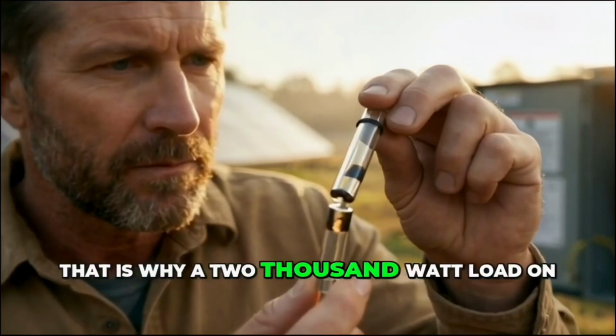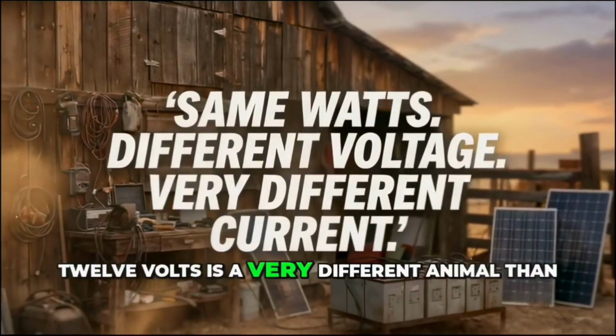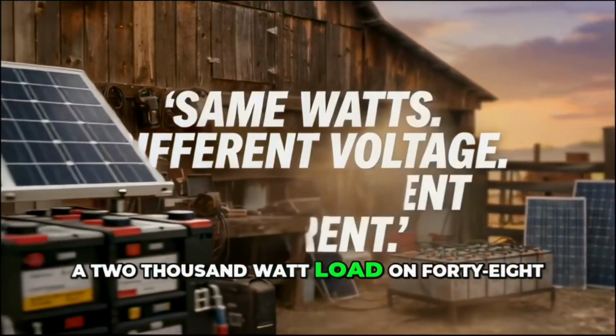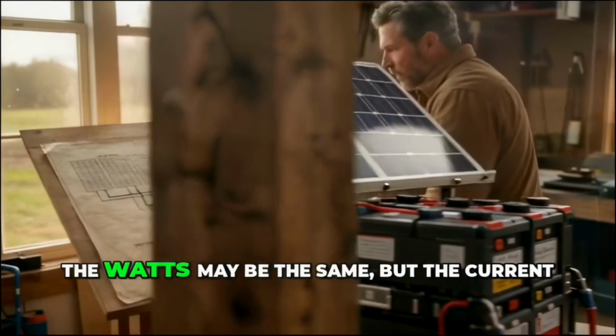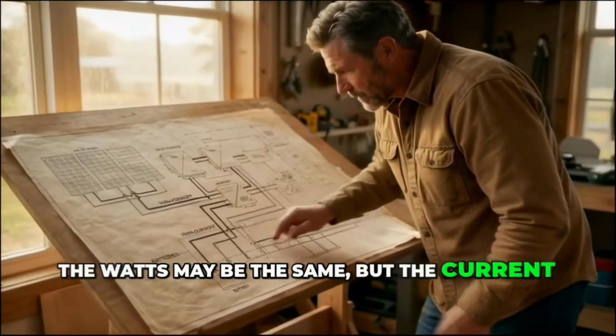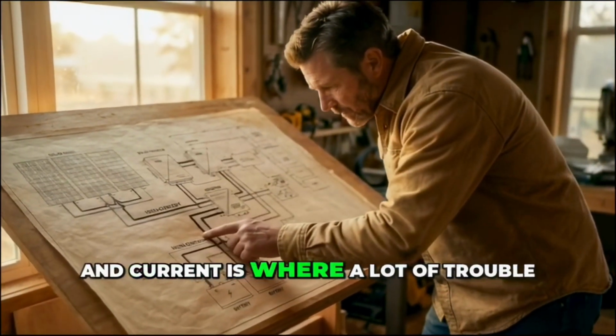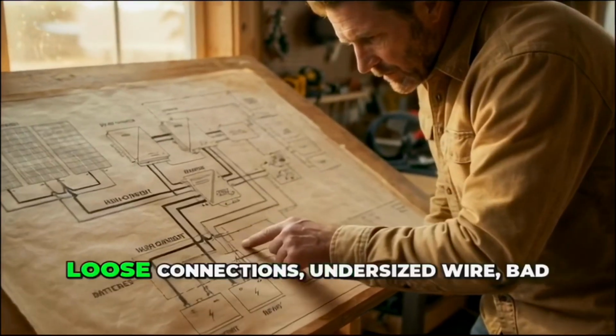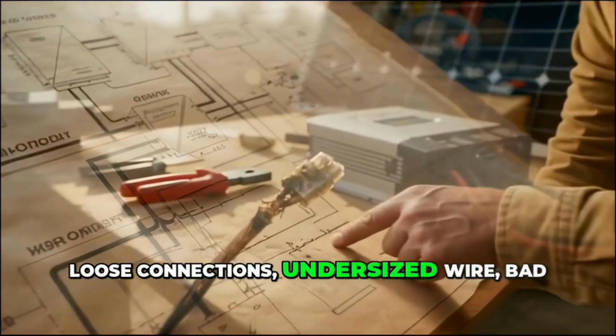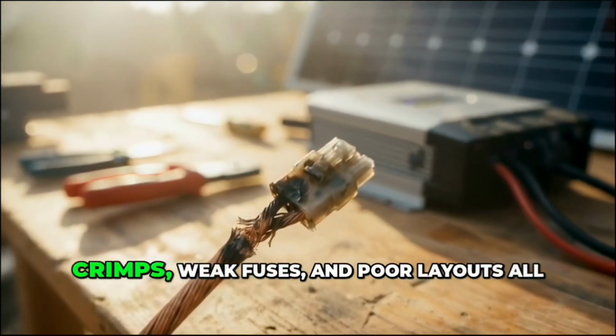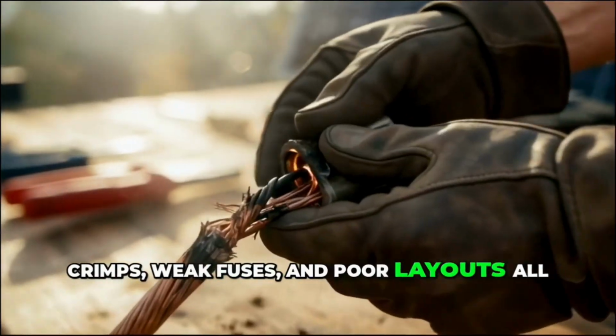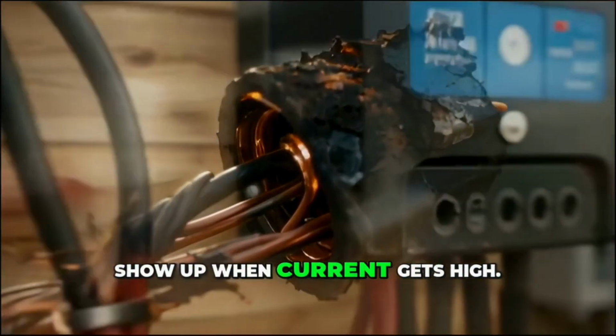That is why a 2,000-watt load on 12 volts is a very different animal than a 2,000-watt load on 48 volts. The watts may be the same, but the current is not. And current is where a lot of trouble starts. Loose connections, undersized wire, bad crimps, weak fuses, and poor layouts all show up when current gets high.